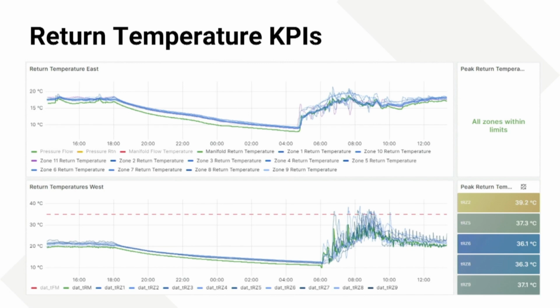This is the return temperature KPIs for that same site. So you see here all the different zones and the return temperatures. There are 2 sides to this site. One site was fitted with radiators and one site was fitted with fan convectors. The site with radiators, we were able to achieve room temperatures with much lower return temperatures, much more stable return temperatures than fan coil systems. The fan coil systems are bringing us alarms of high return temperatures after this day's operation. Because the radiators, the average VART is very low. It's about 16 degrees, 17. It's actually below the room temperature set point because there's a gradient of air in the room. It's that tight.